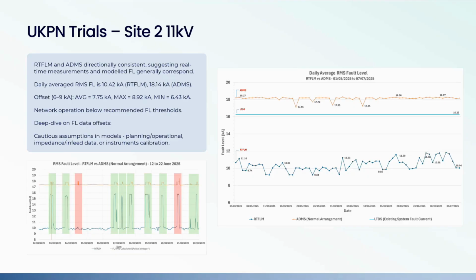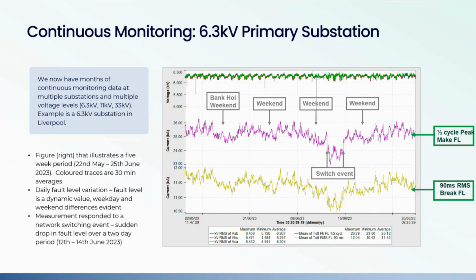The graph at the bottom is a zoom in from the data from the same site. What these red and green boxes depict is that the system was generally corresponding to generation happening over time, and the green boxes show where both changes in the ADMS and the RTFLM, which is the blue line, are closely or almost identically aligned, except for the two cases in the red boxes. So that gave us further confidence in the system operation, and from there we carried on with the remaining 4 installations on our site. I shall pass back to Ralph now, who will present more granular data of what that means. And back to you, Ralph.